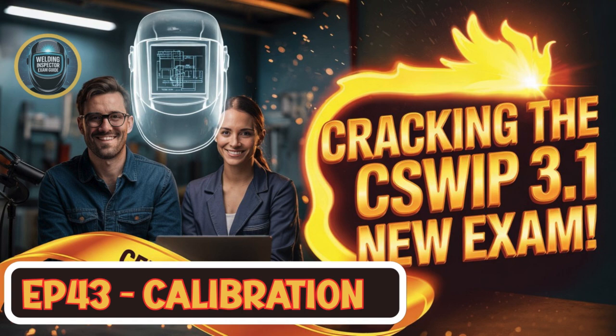And what if something changes? Like if the machine gets repaired, do those timelines shift? Oh, absolutely. They can. You might need more frequent checks based on what the manufacturer says, or maybe your own specific user requirements. And critically, yes, if the equipment has had any repair, recalibration should always happen after that. Right. And of course, if you just suspect something's off, if its performance seems to have deteriorated.